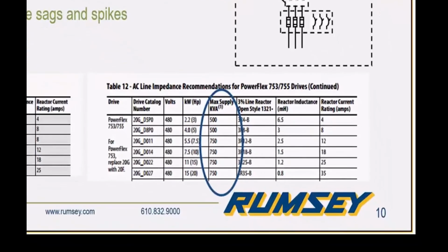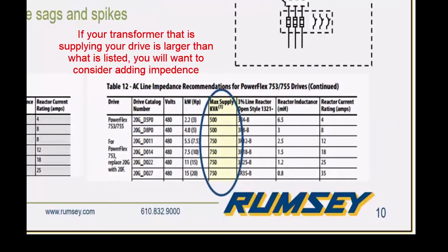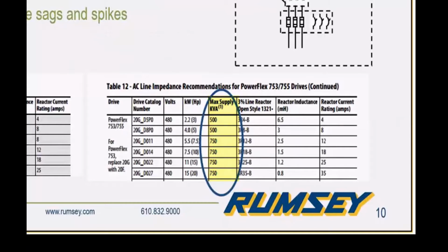So if we look at the table for our particular drive, we can see if our transformer that's supplying it is larger than what is listed there, we're actually going to need to add some type of impedance, and particularly we would add a reactor. In this case, the column to the right of it actually gives you the part number for the required reactor for your drive. So some things to take into consideration here.